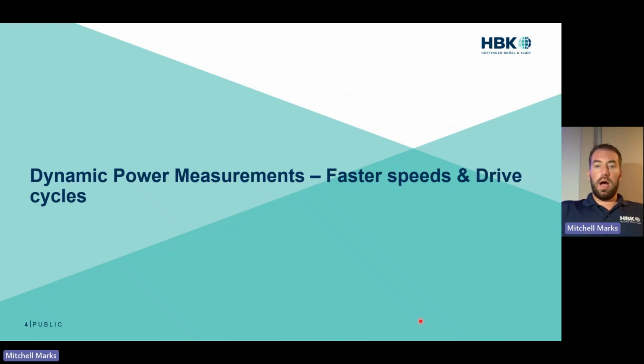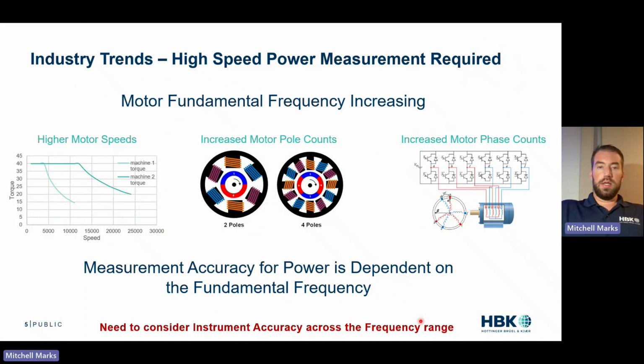So into the good stuff. Dynamic power measurements, faster speeds and drive cycles. We're seeing an industry trend for high-speed motors, which means high-speed power measurement is required, as the motor fundamental frequency is increasing. As motors go to higher speed, as we can go to higher voltages, we can go to higher speeds. We're seeing an increase in motor pole count for a variety of reasons, and also an increase in motor phase counts. This is in both automotive and aerospace. And for all of these reasons, to get the higher speeds with the higher pole counts and the increased motor phase counts, we need to go to a higher fundamental frequency.